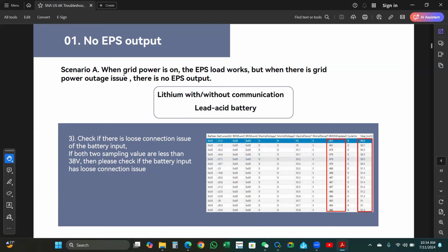Scenario A, when grid power is on, the EPS load works, but when there is a power outage issue, there is no EPS out. Number 3, check if there is a loose connection issue of the battery input. If both sampling values are less than 38 volts, then please check if the battery input has a loose connection issue. What it's saying is you compare the BMS FW update and the VVAT inverter volt. It should be almost the same.